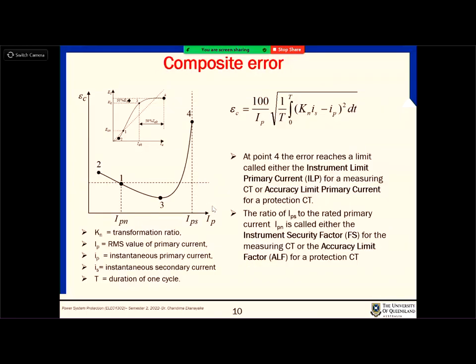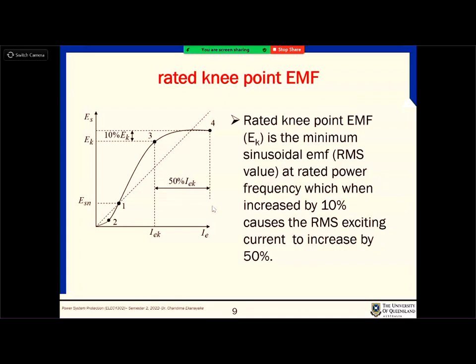So this one is 150% of IEK, that point. And then this point is 110% of EK. Right? So the voltage is increased by 10%, and to bring that about, you need to increase the current by 50%. When you reach that point, we call that voltage the rated knee point. That's because now you are completely deviating from linearity.